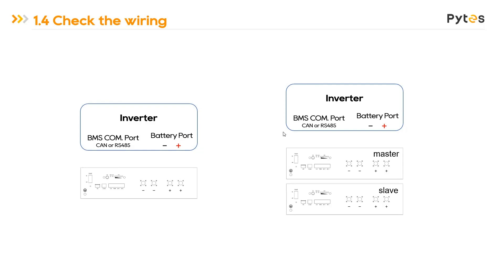Next is the wiring. For installation of one group, it's straightforward: first, move the DIP switch to the corresponding position; second, get the suitable communication cable per your battery version and connect the battery to the inverter; third, connect the power cable, positive to positive, negative to negative. For multiple batteries it's almost the same — set the DIP switch, but you don't need to change it on slave batteries. Then connect the two batteries using the standard communication cable, link 1 to link 0, and link the master battery to the inverter with the suitable cable. Last, connect the power cable.